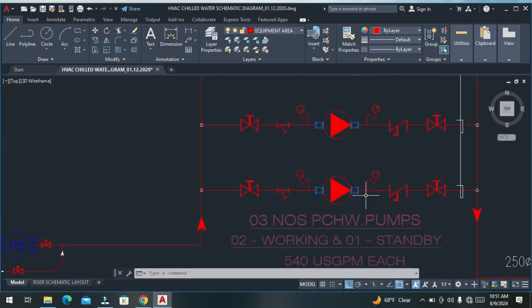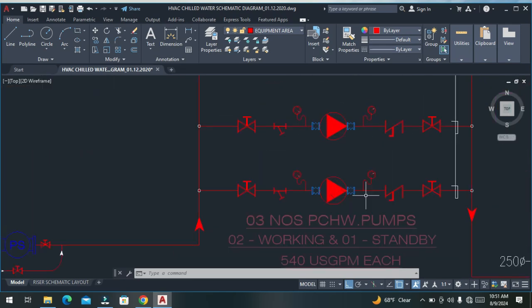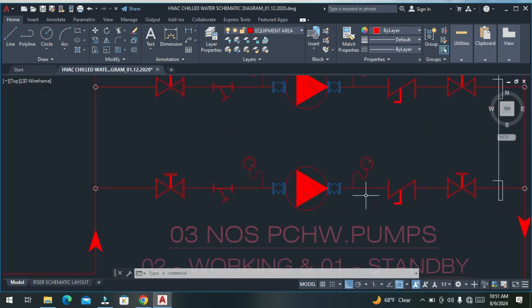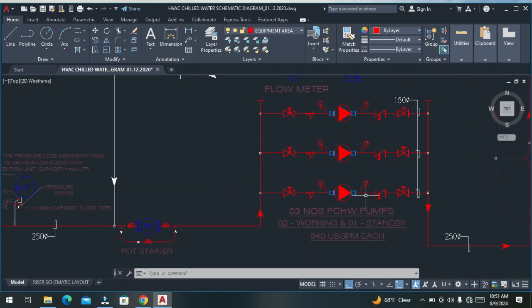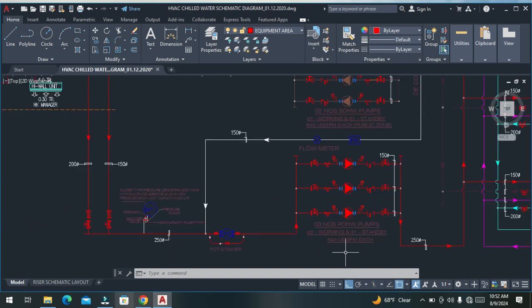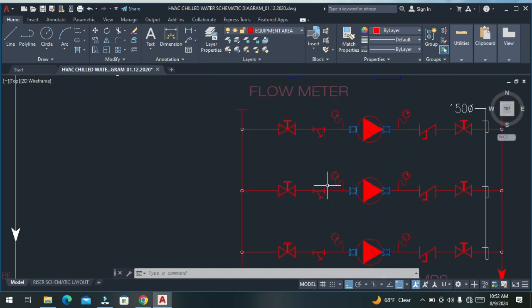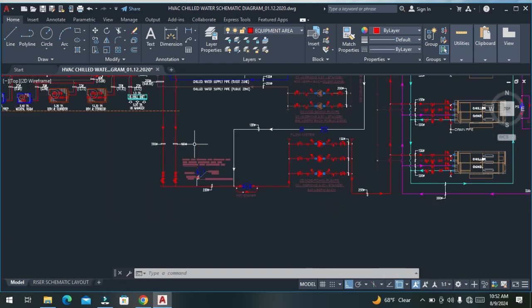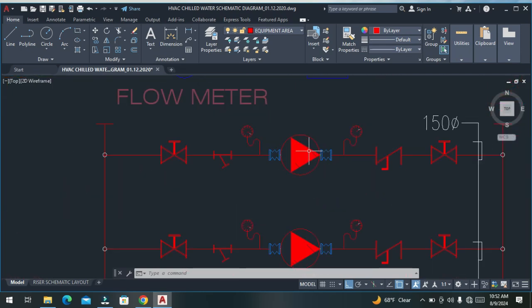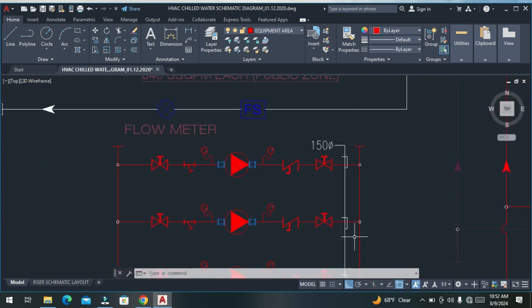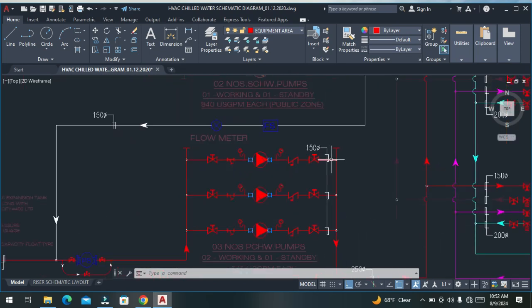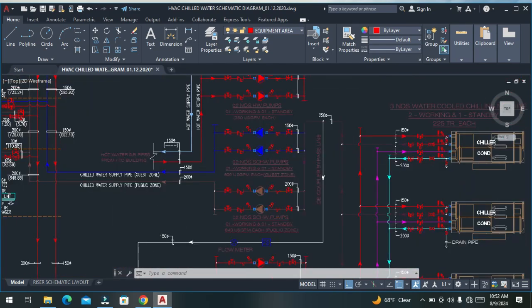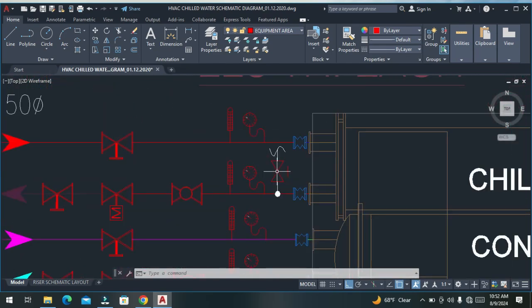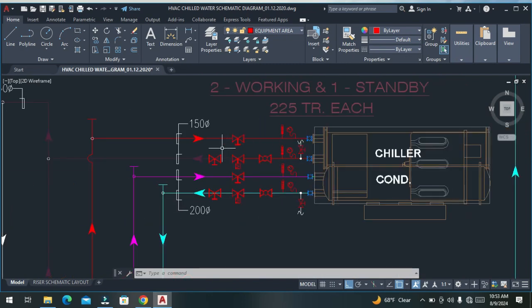To the suction of the primary pumps. Here we have one more pump added, which is the primary pumps. Here we have 3 nos. of primary pumps. Its capacity is 540 GPM. 2 are working and 1 is standby. So what is the use of these pumps? Actually it takes the chilled return supply line water and gives it to this evaporator. From here it goes in, and from the output of these primary pumps it goes to the header, and then it enters into the evaporator in. So here, evaporator in.